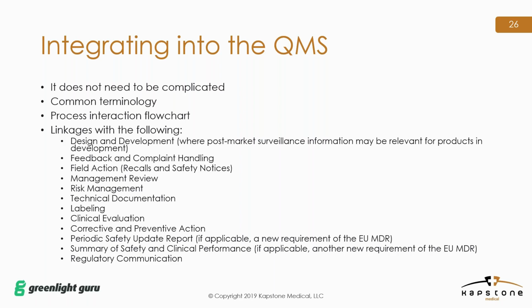So the following are linkages that you need to consider. They were not all considered in my quick flow chart, but you need to sort of take into account design and development. So if post-market surveillance information may be relevant for products that are in development right now, you need to consider that. Your feedback and complaint handling process, your field action process, management review, risk management, your technical documentation procedure, labeling, clinical evaluation, CAPA, any of your reporting requirements, your summaries, and then any regulatory communication. So this is just showing you some of the linkages that you may need to consider.